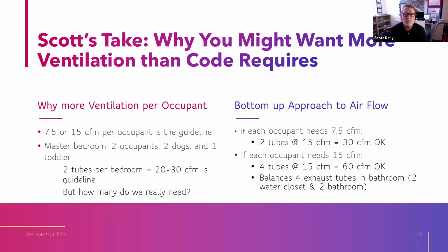So often we'll put 2 tubes into the bedroom. And why 2 tubes? Because we have the 15 CFM if we're doing the 7.5 for those 2 people in there. But then we really have to look at it like who's really in there. And so for sure we need 2 tubes. We need 30 CFM. And so that's kind of why I have that calculation, or I really believe that that's the answer. That's how many we need.